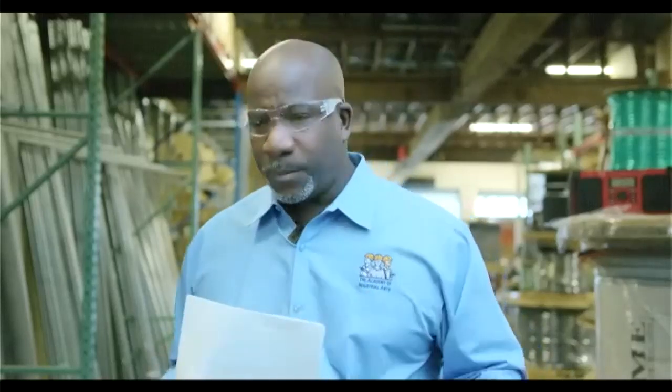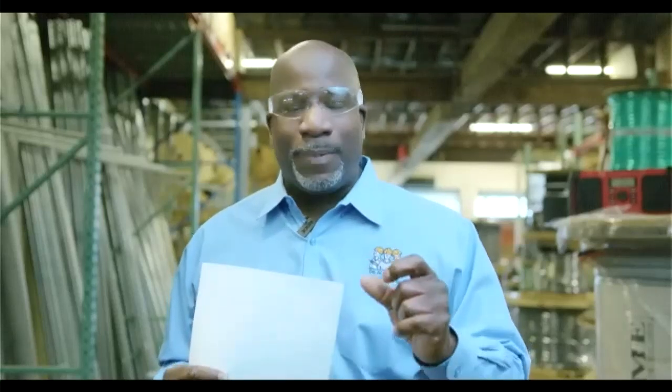Then the other form of accessibility is applied to wiring methods. Any junction box or electrical fitting that has a removable cover that houses conductors should always be accessible. We can't put junction boxes behind drywall or any building material and render it inaccessible. So there are three forms of accessibility in Article 100.